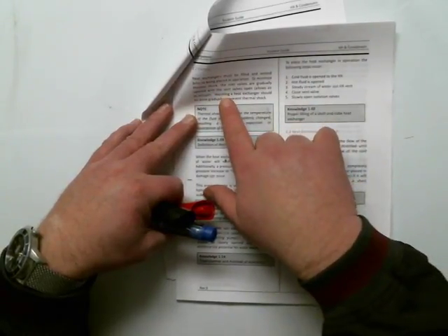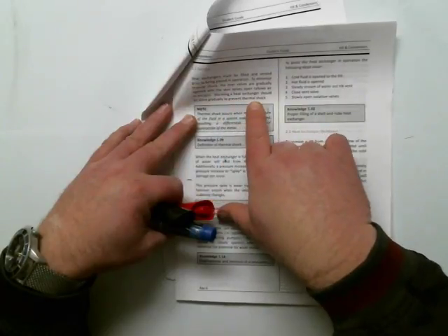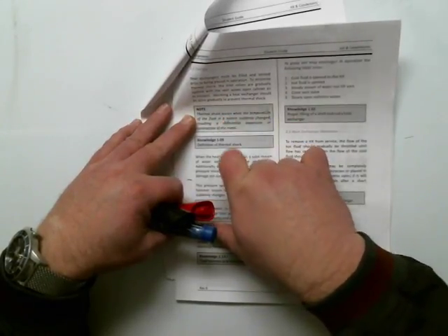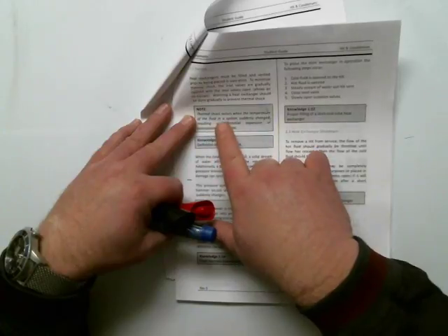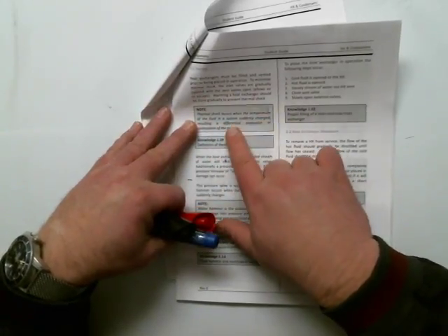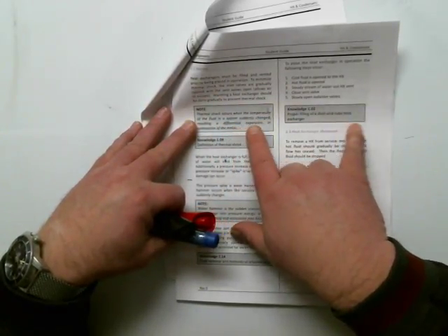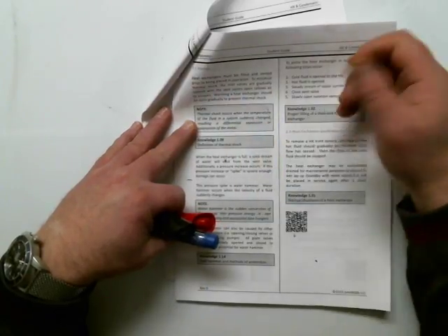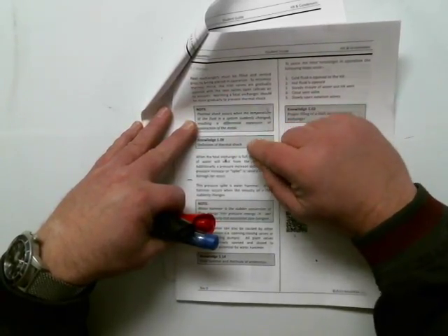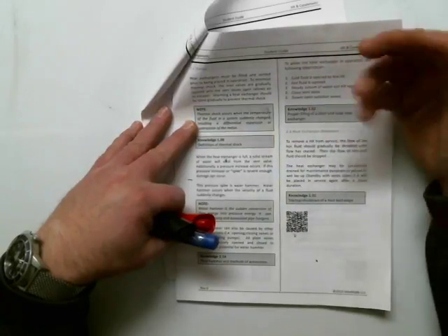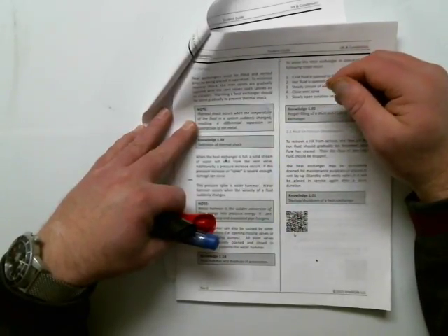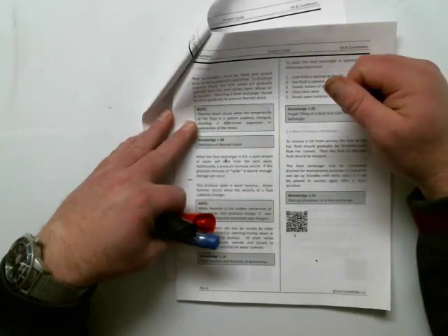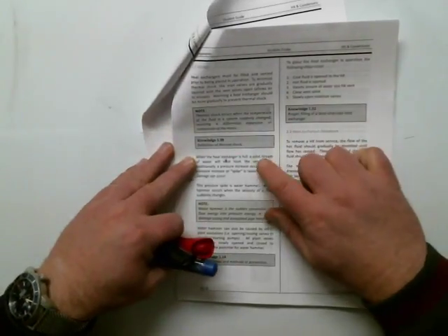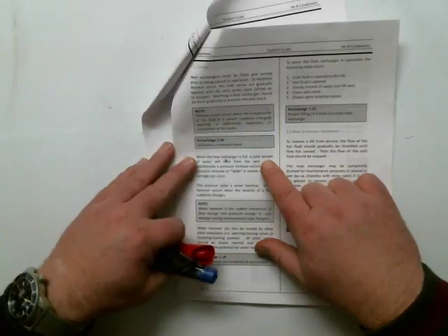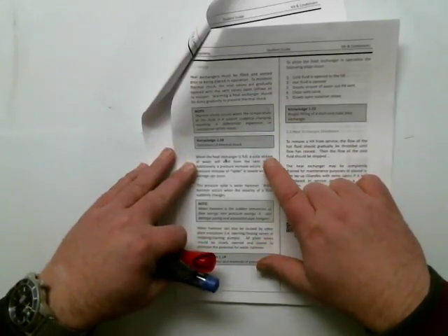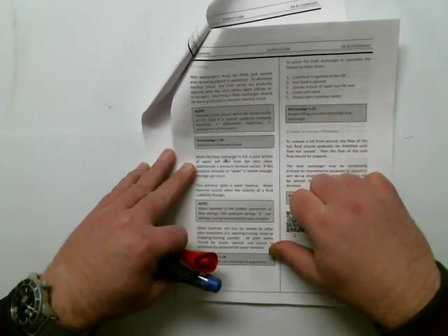So it says the warming of a heat exchanger should be done gradually to prevent thermal shock. And it tells us what thermal shock is here. It occurs when the temperature of a fluid in a system suddenly changes, resulting in a differential expansion or contraction of the metal. And that can be damaging. So there's the definition of thermal shock, and we want to prevent it by gradually introducing the hotter fluid after we've filled and vented the cold side. And it says when a heat exchanger is full, I will see a solid stream of water being emitted from the vent valves. So that's cool.